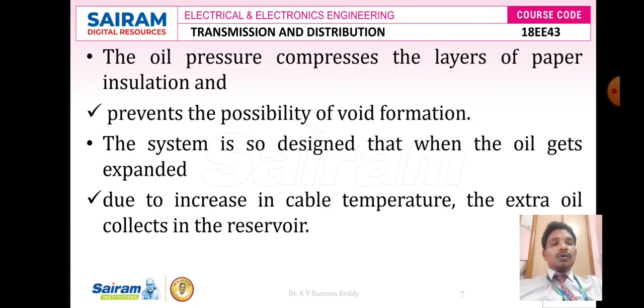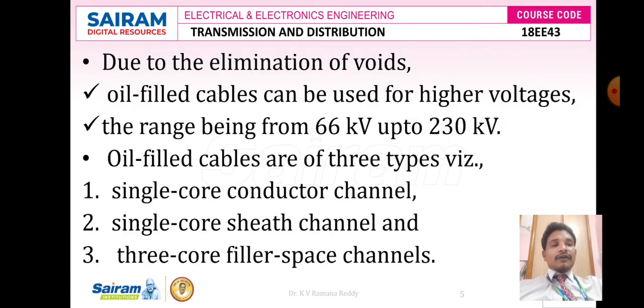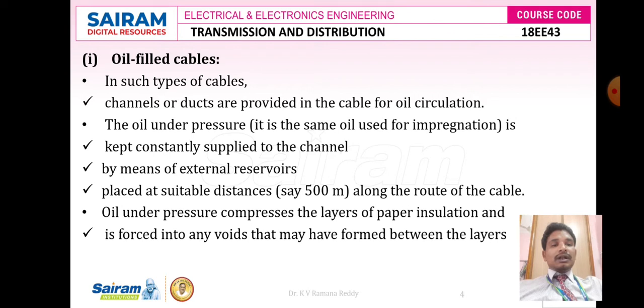Here we are pumping that oil to overcome the voids which take place in the paper insulation. To pump this oil it requires external reservoirs. The external reservoirs are placed at a suitable distance of 500 meters along the route of the given cable. Oil under pressure compresses the layers of paper insulation and forces into any voids. If it forcefully pumps oil into the voids, then there are no electron pockets and no leakage currents, thereby we can increase the dielectric strength of the given insulating material and overcome short circuit faults.